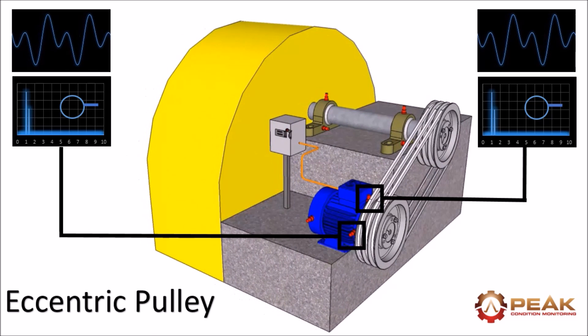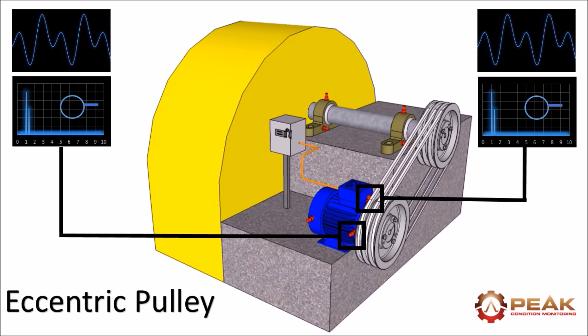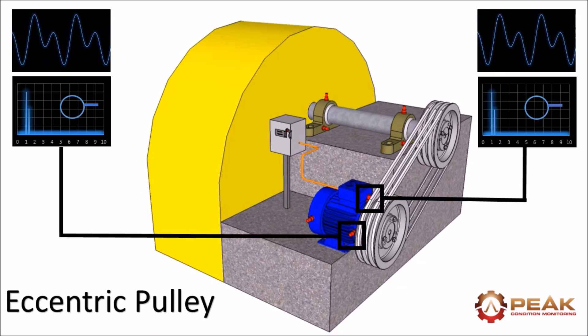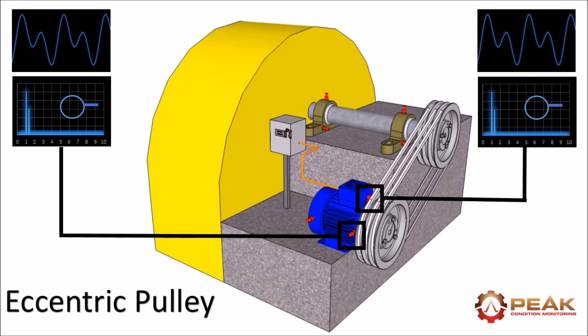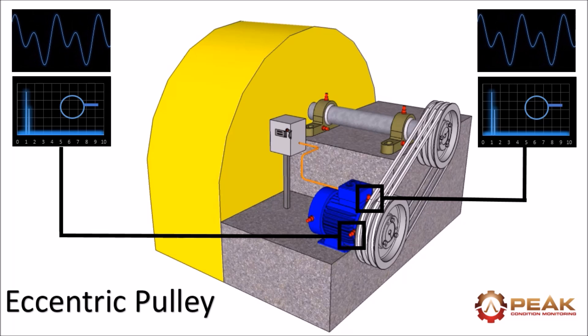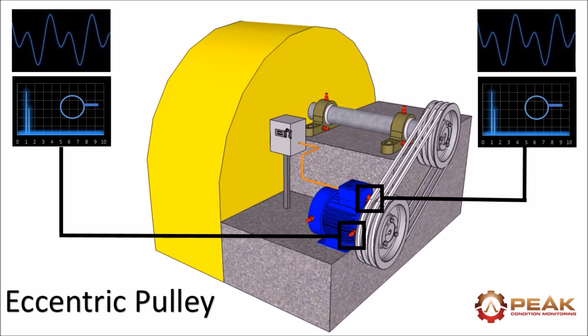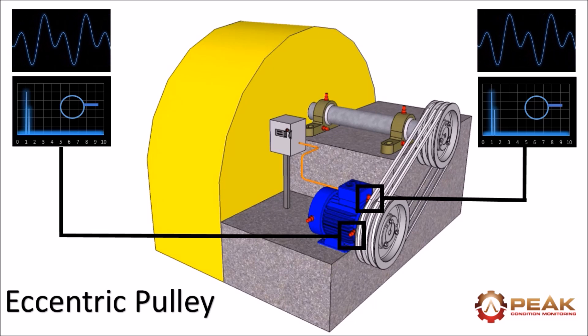Phase can also help to determine the presence of eccentricity in a pulley for example. In this situation the problem would present as two peaks in the radial vibration spectrum. One at the motor speed and one at the fan speed. If the pulley was eccentric the phase of the waveforms would be the same.